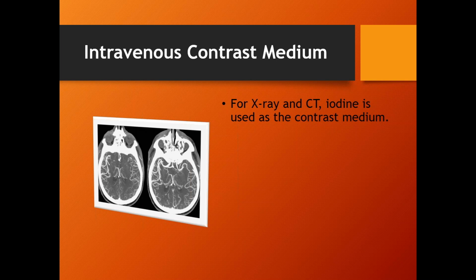So whereas X-ray and CT injectors use an X-ray tube, radiation passes through the patient and strikes detectors on the other side, like we described earlier. For X-ray and CT, the two types that use the same technology, the fluid in this syringe that makes these images happen is clear. It looks like water, but it's not. It's an iodine-based fluid. The secret ingredient in a contrast for CT and X-ray injectors is iodine.